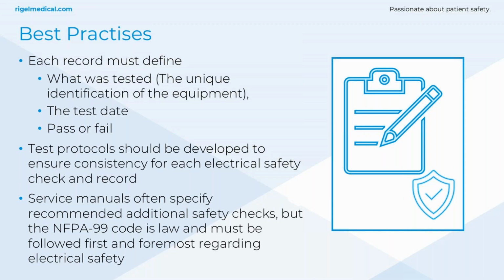The main aim of electrical safety in NFPA 99 and that of all electrical safety testing standards is just to limit leakage currents that can cause injury or death to a patient or any other user within the facility. So it's always best just to practice testing where a risk of electrocution may occur, regardless of what the minimum requirements are of any standard or code. If you do have any doubts, it's worth looking at the OEM requirements, whether that be in the service manuals or PMs. As it states here at the bottom, service manuals may specify checks, but NFPA 99 is the law, and it must be followed first and foremost regarding electrical safety.